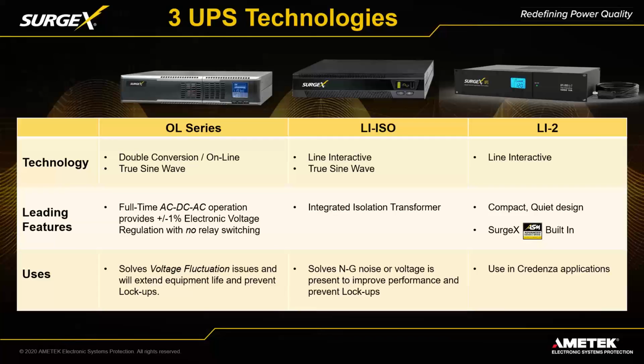That's the full time double conversion you've heard us talk about many times. It takes the AC coming out of the wall and turns it into DC. In DC mode it's charging the batteries, but the AC to DC converter is also strong enough to power the inverter stage, the DC to AC operation. So with the OL series, we're regenerating the power right on site, and it has many positive attributes, one being no relay switching—when the power goes out, the battery takes over instantaneously since there's no relay inside.